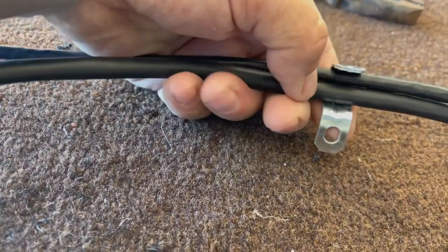From this point on, it's very critical that you're very careful with your transducer wire. There are a ton of tiny wires in there, and if you damage them, you're going to have issues immediately - you'll know, you won't get an image. So what I'm doing here, I'll show you.